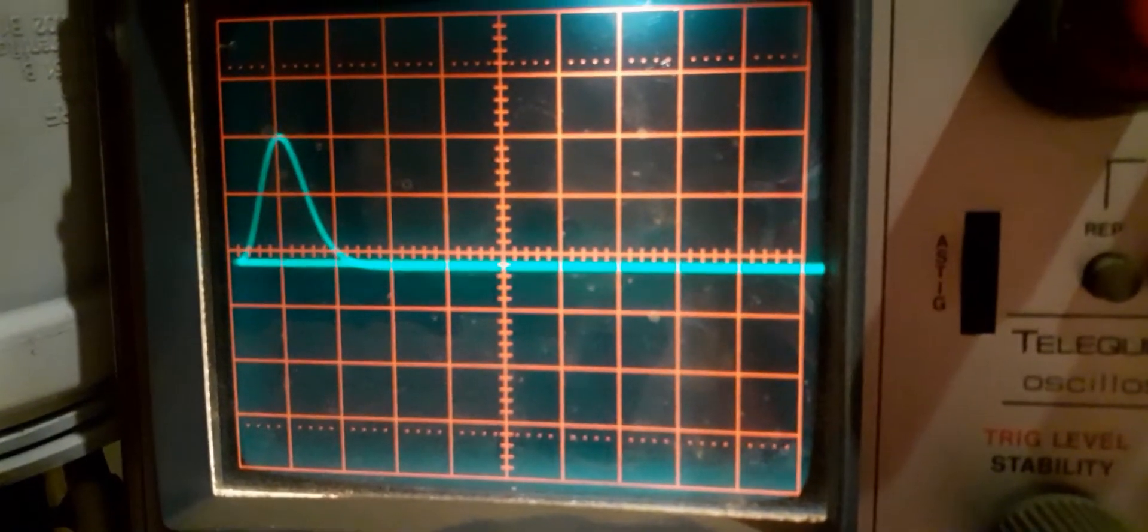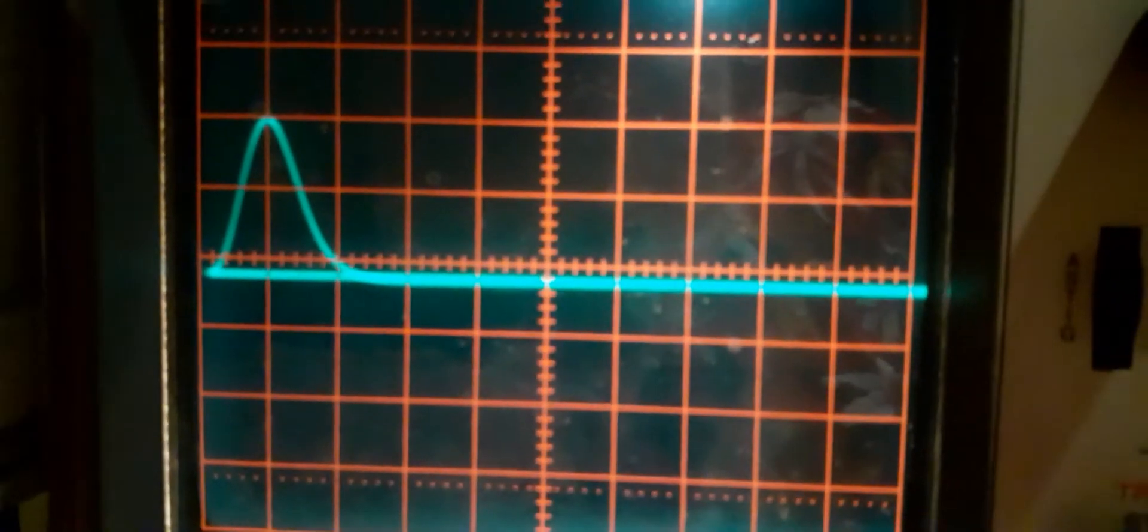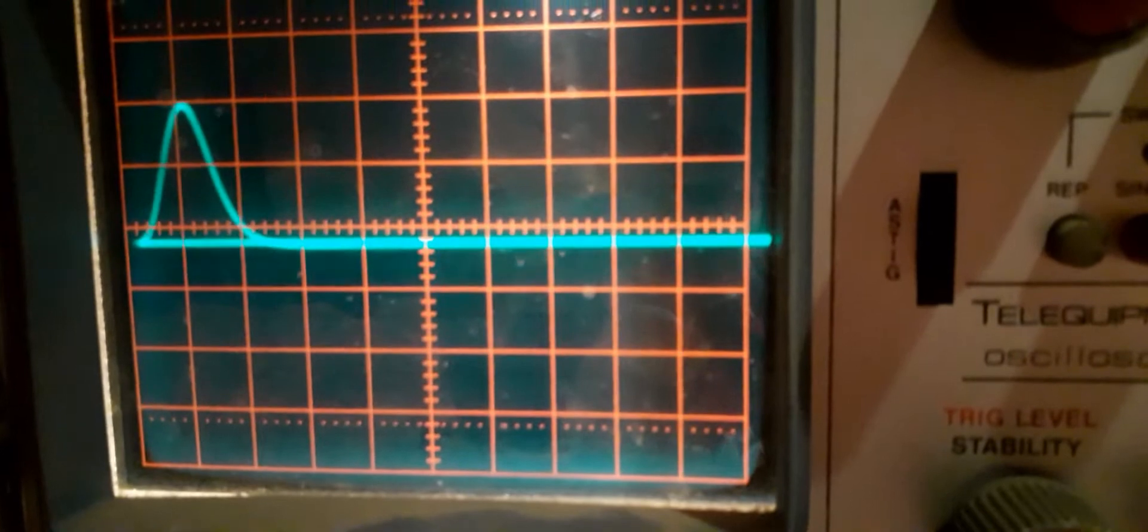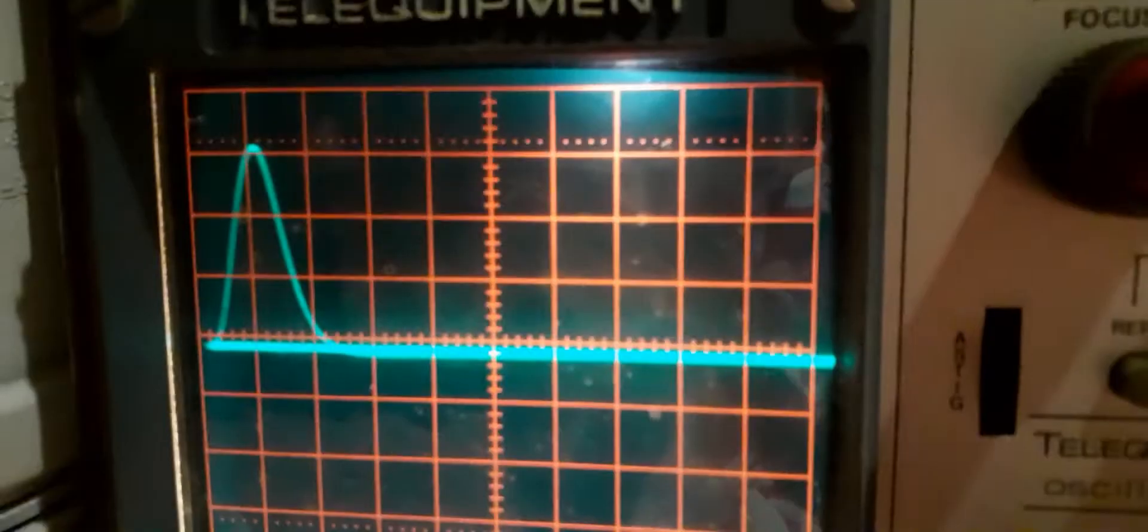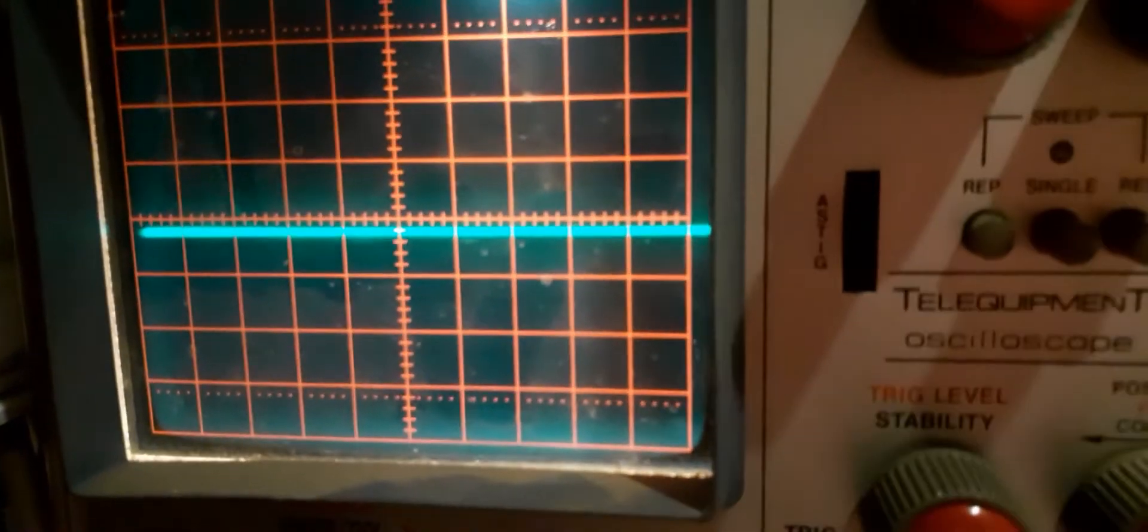And would you look at that. Let's see if we can trigger on that. That is exactly what you want a nuclear pulse to look like: almost symmetrical with no undershoot. Let's vary the pulse height. We are at one volt per division by the way. This is a very working instrument. The only thing I did on this instrument when I got it was changing the electrolytic capacitor that leaked—otherwise the instrument just worked fine.